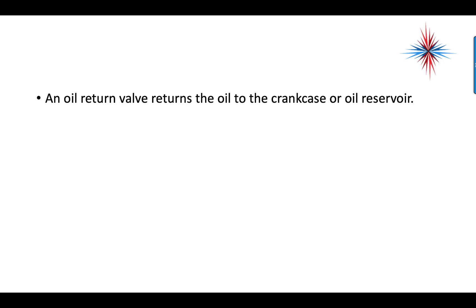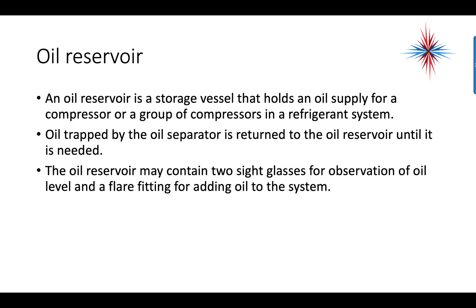An oil return valve returns the oil to the crankcase or oil reservoir. An oil reservoir is a storage vessel that holds an oil supply for the compressor or a group of compressors in a refrigeration system. Oil trapped by the oil separator is returned to the oil reservoir until it is needed. The oil reservoir may contain two sight glasses for observation of oil level and a flare fitting for adding oil to the system.